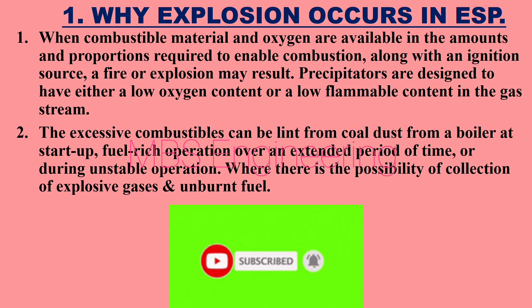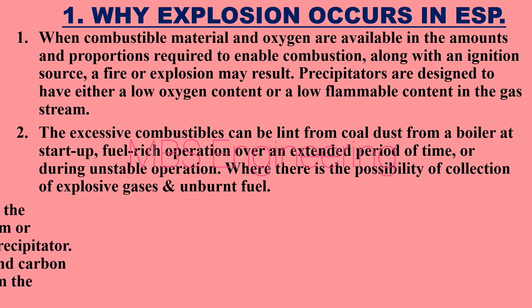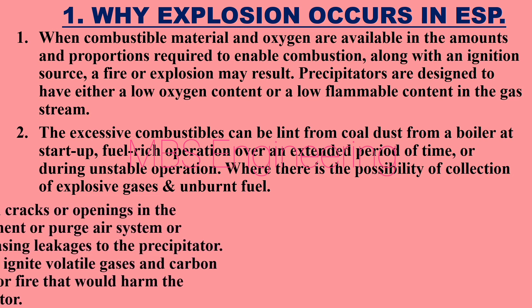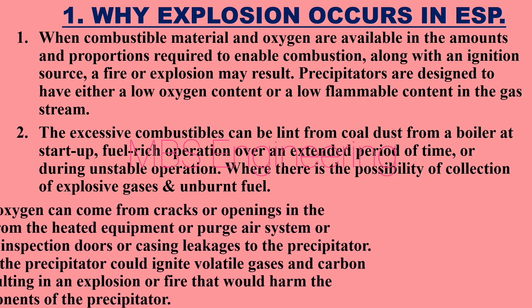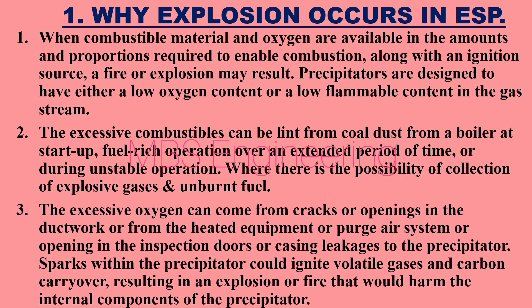Excessive combustibles can also arise during unstable operation, where there is the possibility of collection of explosive gases and unburnt fuel. Point 3: Excessive oxygen can come from cracks or openings in the ductwork, from heated equipment, the purge air system, or leakages in the inspection doors or casing. Sparks within the precipitator could ignite volatile gases and carbon carryover, resulting in an explosion or fire that would harm the internal components of the precipitator.